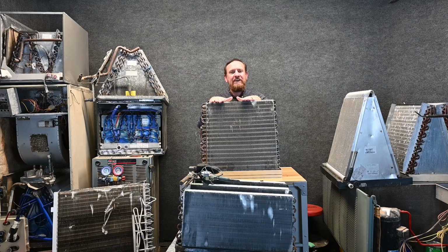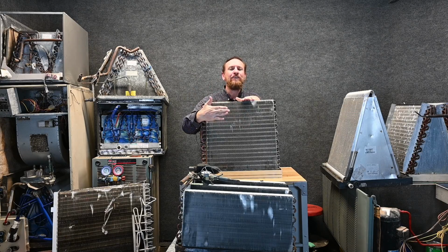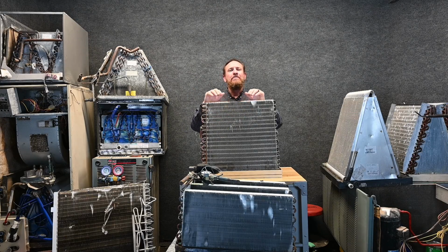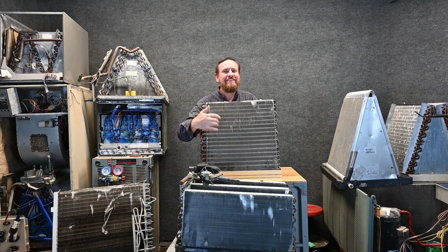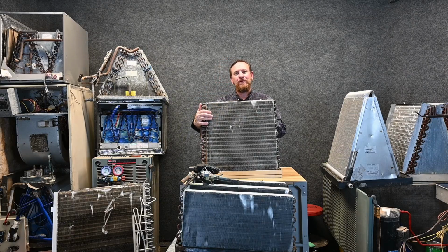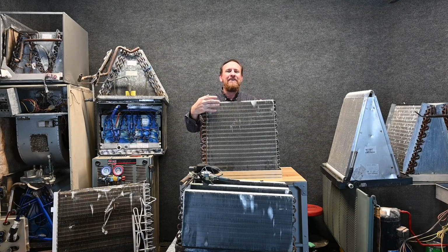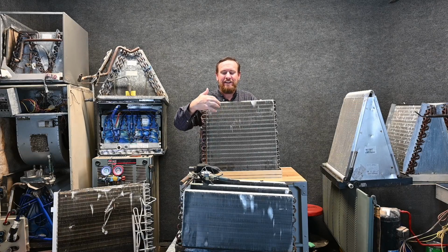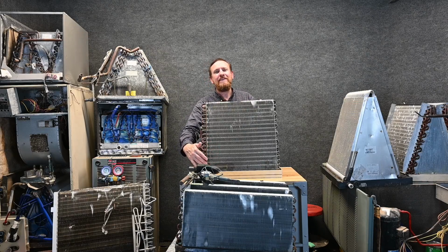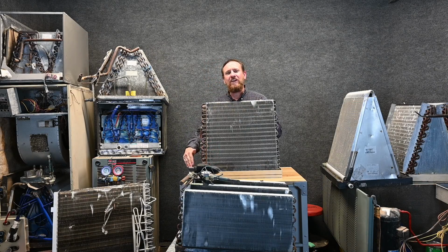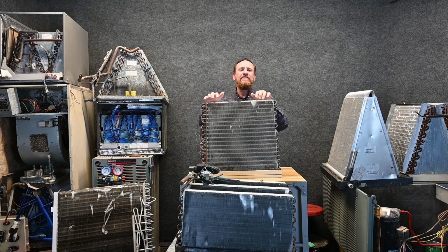So on the evaporator side, we're absorbing two kinds of heat. We're absorbing sensible heat, sensibly changing the temperature of the air, and we're also latent cooling the air, pulling moisture out, making that water vapor change from a vapor to a liquid, and that liquid condenses on the fins of this evaporator coil. Inside it's an evaporator coil, but outside the moisture from the air is condensing on it. So that water condenses and runs down these fins into the condensate drain pan, runs out the condensate drain line, and is physically removed from the house. So we're literally pulling moisture out of the air.